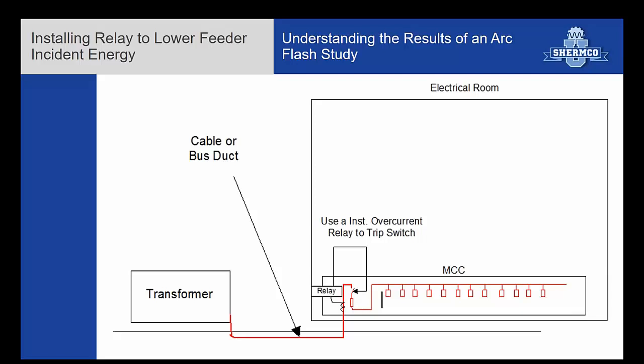So once again, we see on these lineups that have a big fuse disconnect feeding all the other disconnects, we see where the whole bus is dangerous. A lot of times these fuses do have a shunt trip device that allows the fuse switch to be open, but the problem is most of the time it's 6 times rated. So if this is a 2500 amp switch, it's only allowed to interrupt 6 times that current, which is not enough to necessarily open safely under a fault. So it becomes very hard to put a relay and trip that switch.